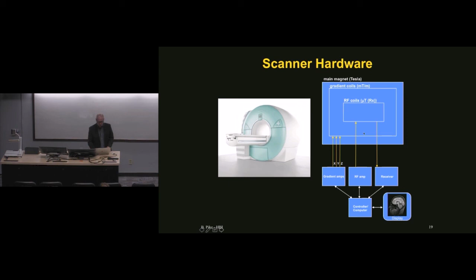They're superconducting solenoid designs by and large. There are some differences, but the most common ones you'll see are basically a big toilet paper roll with wire wrapped around it. The wire is typically a niobium titanium alloy that's many kilometers long, immersed in liquid helium, which has a boiling point of minus 269 Celsius.